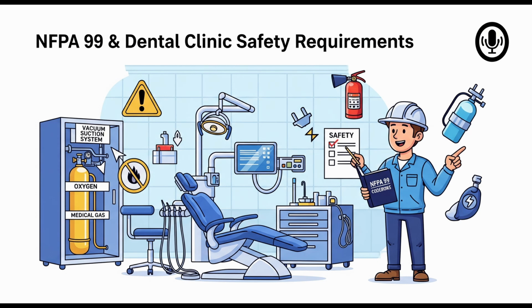That makes sense. And each outlet or inlet needs two valves, essentially. A primary valve you operate, and a secondary valve that automatically closes and seals the pipe when you remove the primary valve assembly, the part you plug into. This lets you service or change equipment at one station without shutting down the whole system or even other outlets in the same room. The requirements for Cat 3 outlets are in 5.3.5 and 15.4.2.7.